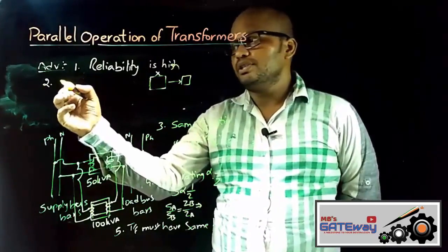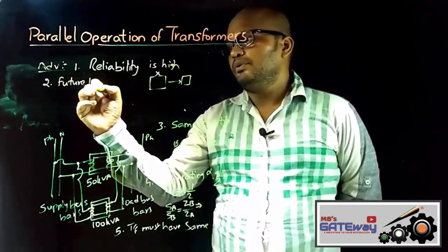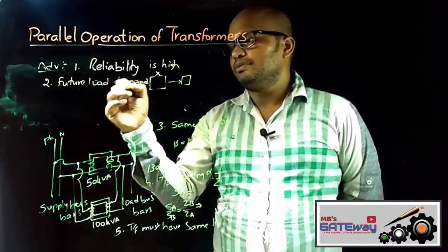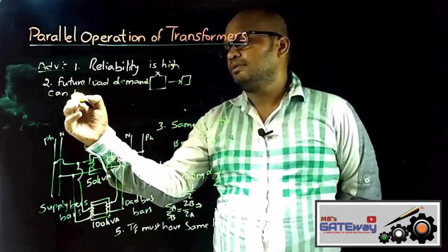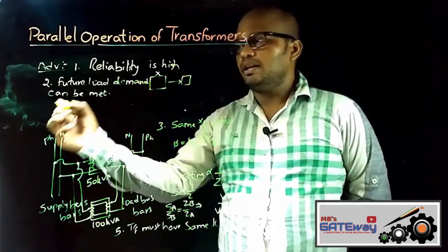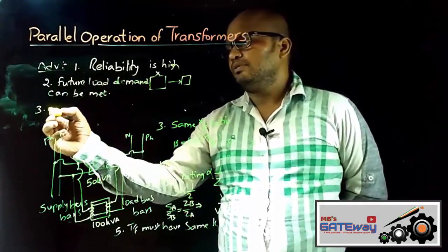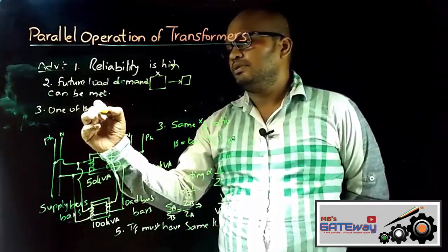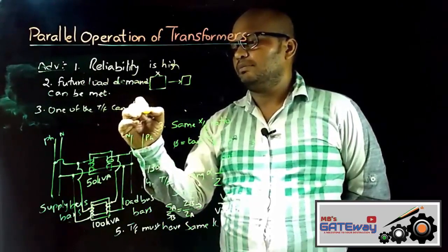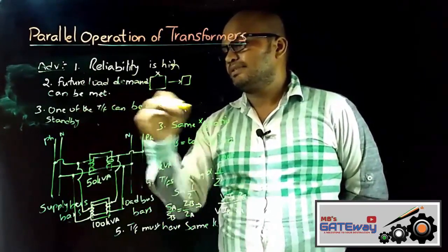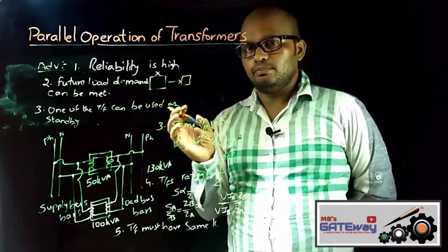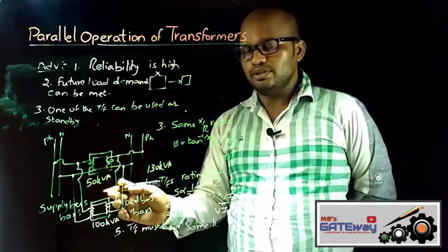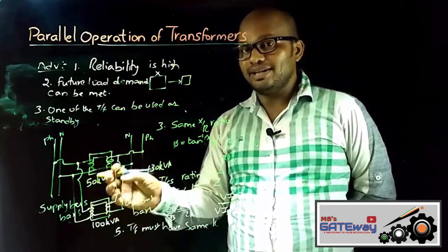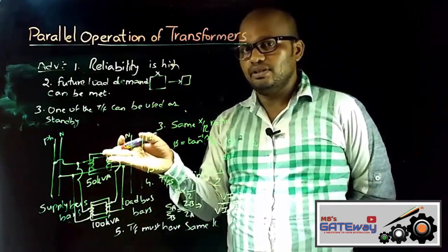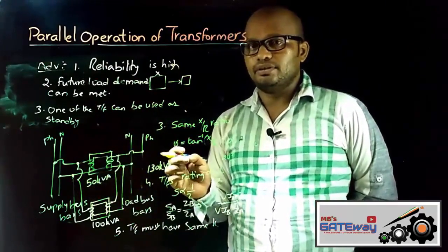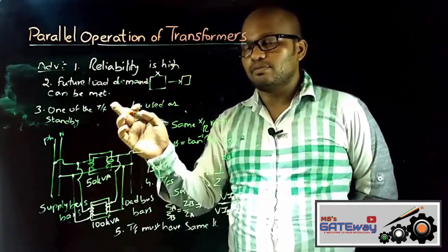And the second advantage is that future load demand can be met. And in parallel operation of transformers, one of the transformers can be used as standby. That is, even if there is no requirement of two transformers for supplying power to the load, one transformer is used as standby for safety purposes, because if one transformer fails, then continuous supply can be maintained through the other transformer. So in parallel operation of transformers, one of the transformers can be used as standby.